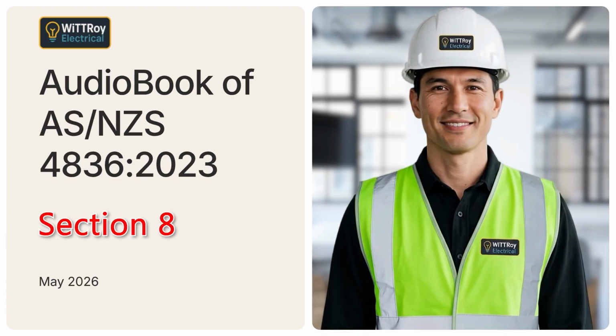Clause 8.5.1. Barriers. Clause 8.5.1 explains barriers. Barriers must be made from material that effectively separates a person from adjacent energized electrical equipment. Barriers must be visually inspected for defects before and after each use. If a barrier is defective, it must be tagged and removed from service. Warning signs should be placed beside barriers or form part of the barriers where barriers are used to prevent accidental access to areas where electrical work is being performed.